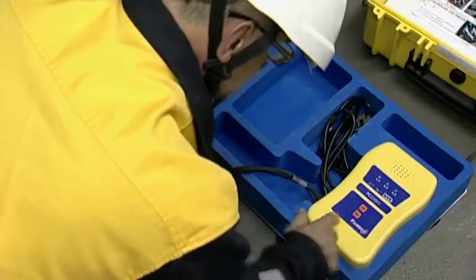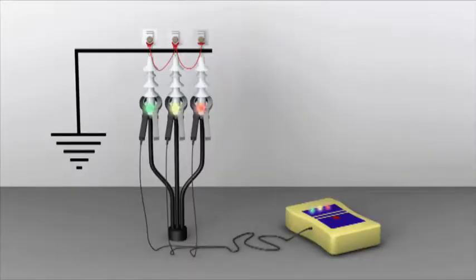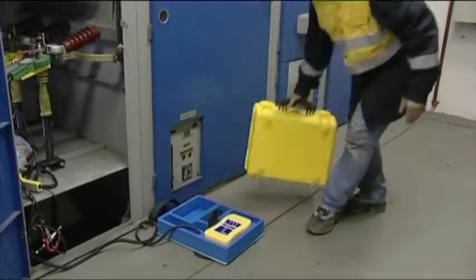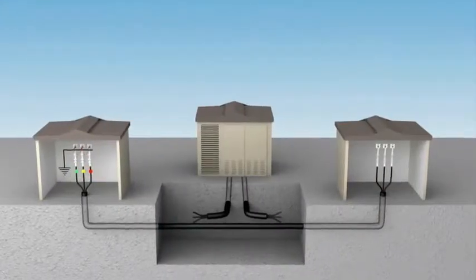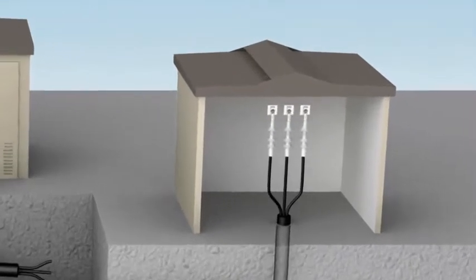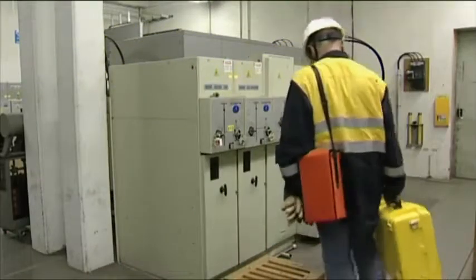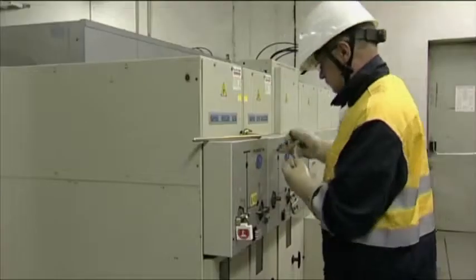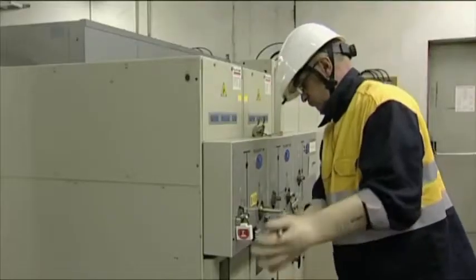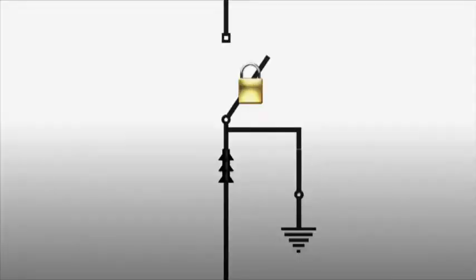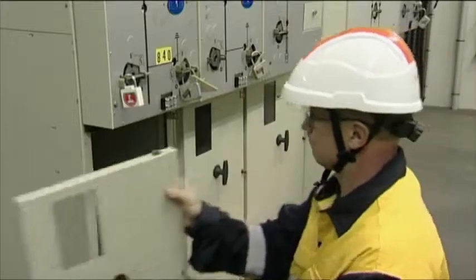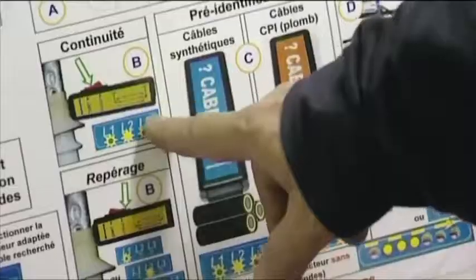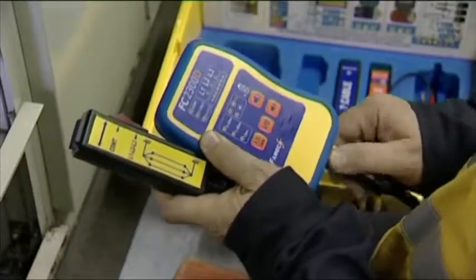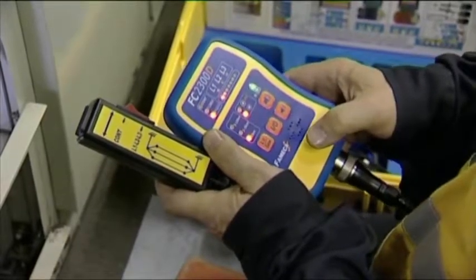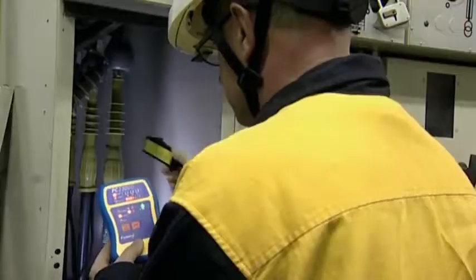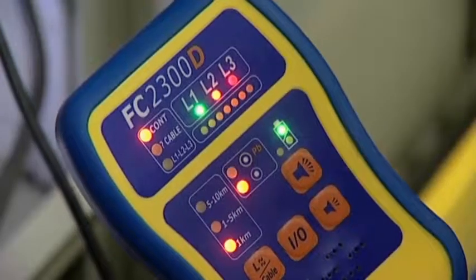FC2300 cable identification. Once the clamps have been placed on Substation 2, go back to Substation 1 to close the grounding switch and finalize cable grounding. The signal transmission circuit is established by closing the two grounding switches. Once they have been closed, we can check the continuity. Reception of the warning sound confirms we're on the right circuit on which work is to be done.